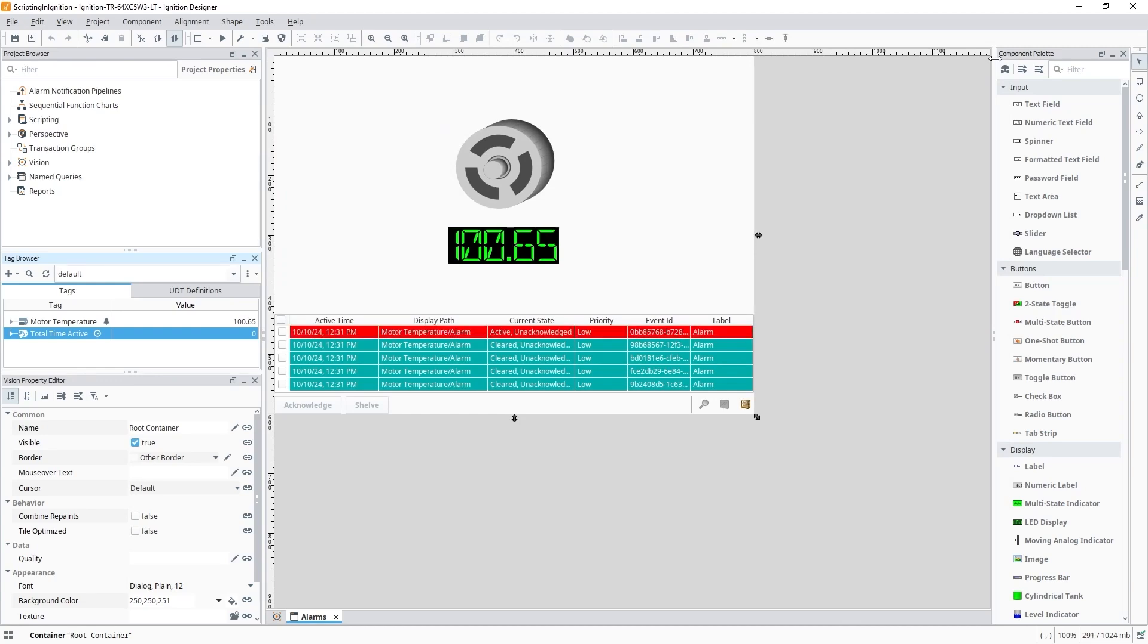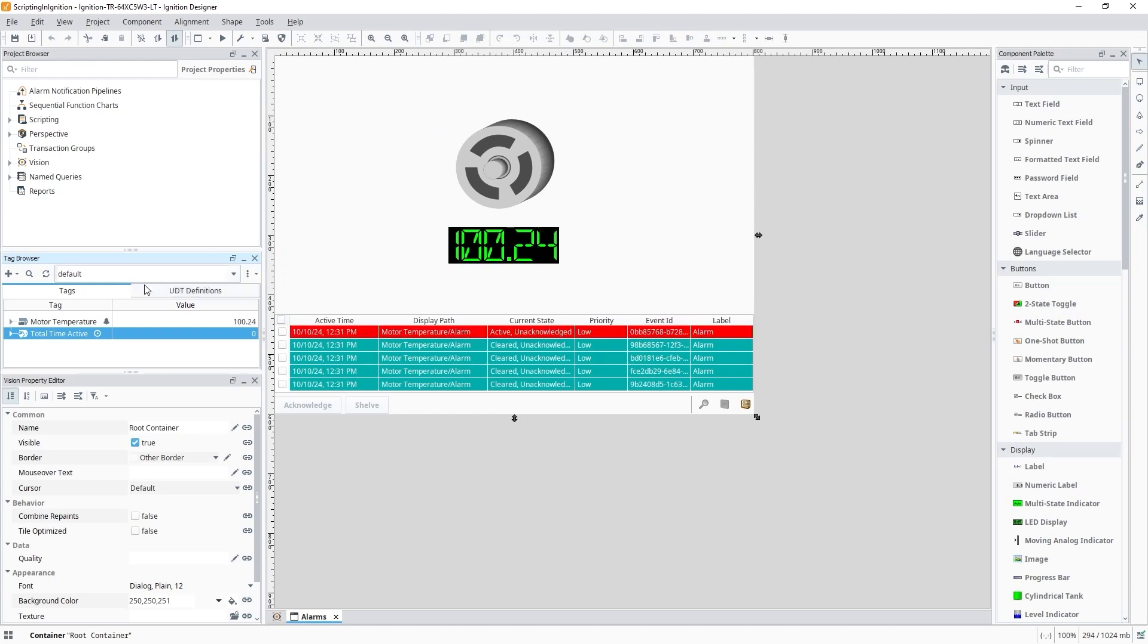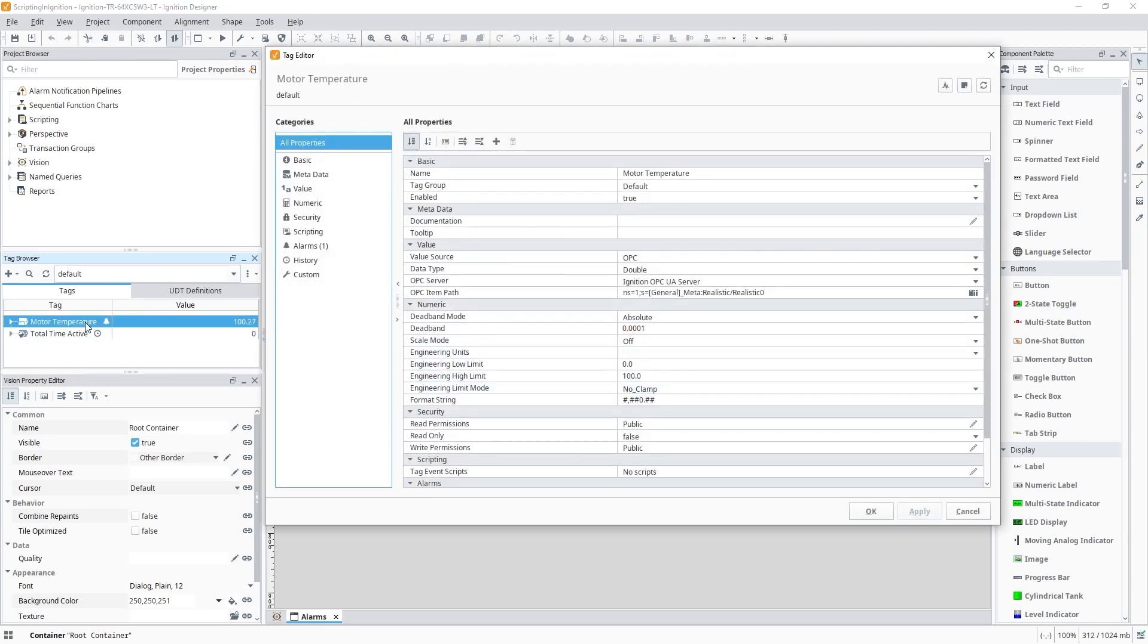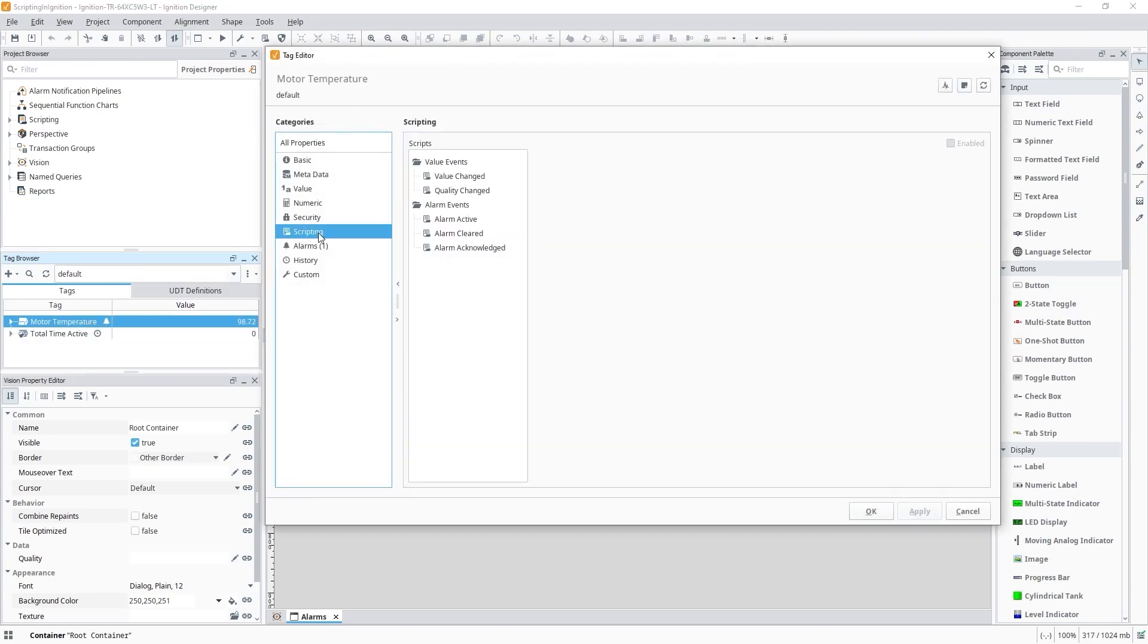What I'd like to do is use the alarm's data to calculate the amount of time the alarm was active. Let's make use of the alarm event scripts on the motor temperature tag by first editing it and then go into the scripting category. We'll make use of an alarm-cleared script.